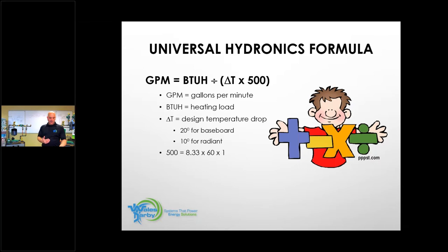On page 44, if you scroll down just a little bit in that TACO guide, it gives you the BTU per hour at 68 degrees. If I have 30% glycol, or 50% glycol in there, it will break it down. If it's straight water at 68 degrees, it's 500. If it's glycol at 30% at 68 degrees, it's 445 would be my new number times my delta T. If I'm using antifreeze, I normally don't want to go over 50% on any manufacturer's boiler. That's usually their rule, not my rule. So understand, if you're using antifreeze, your BTU is going to be a little less, because that antifreeze is going to want to reject the heat a little bit.